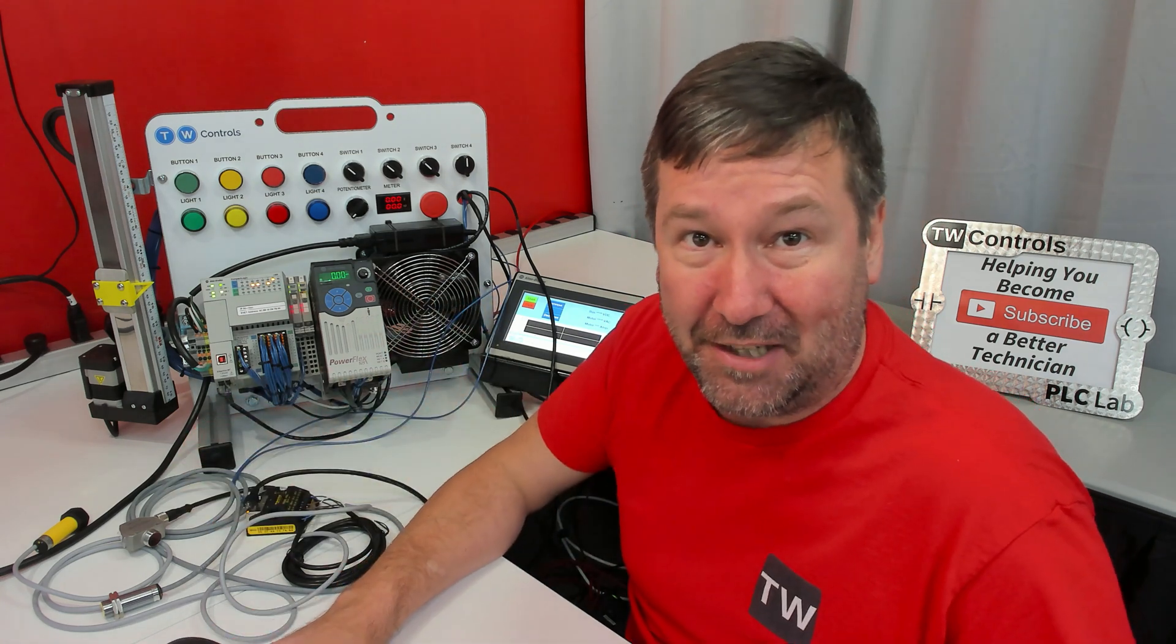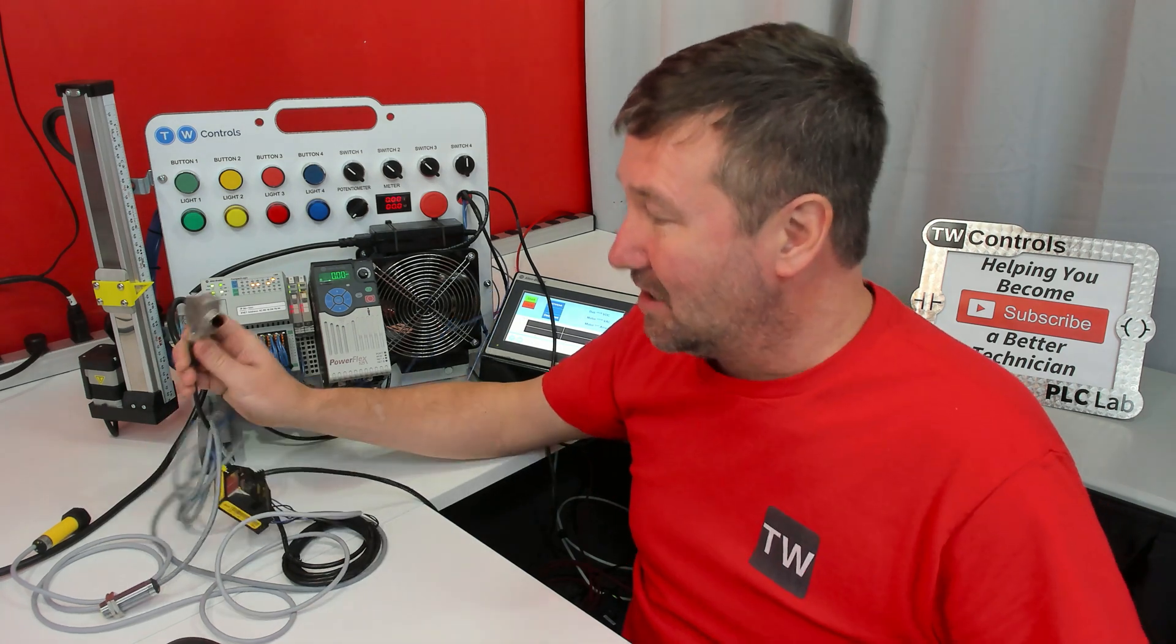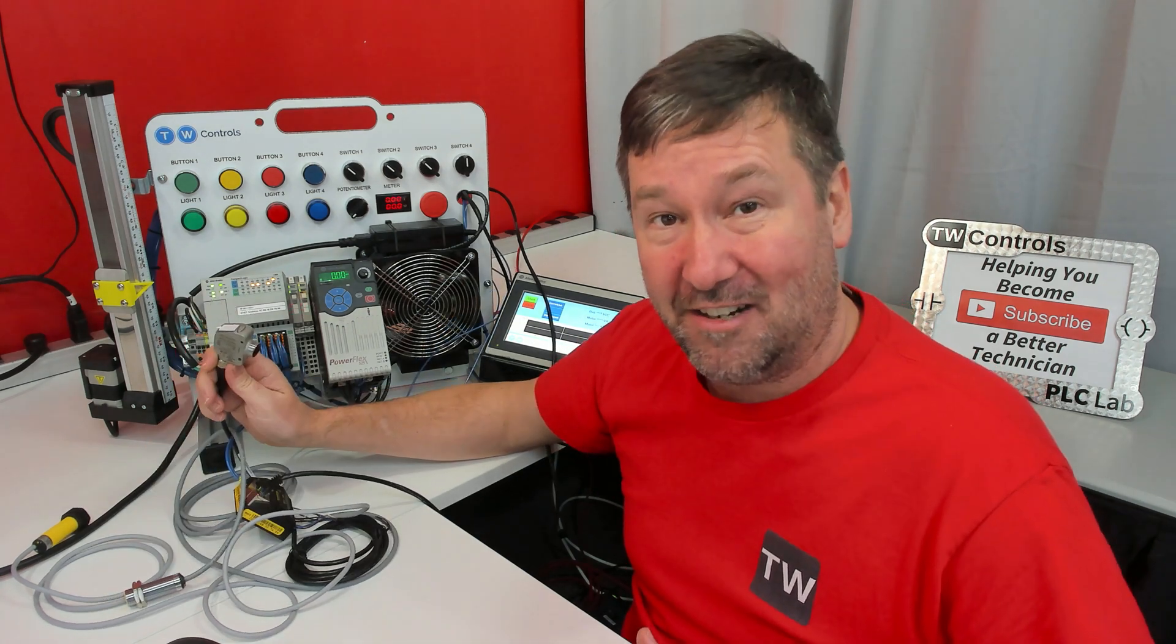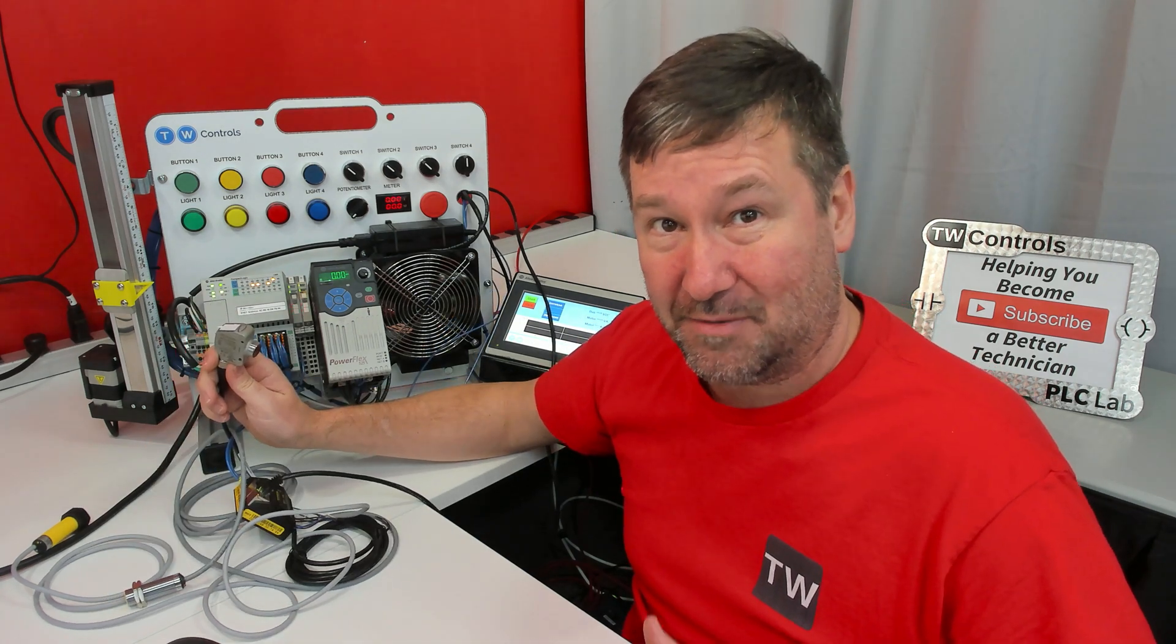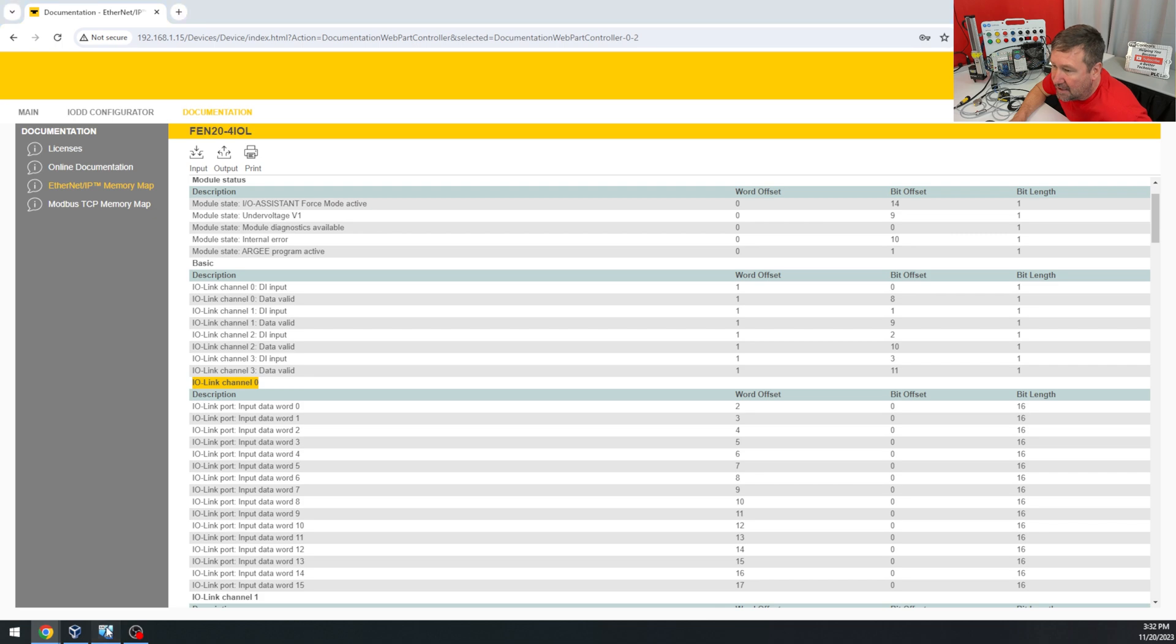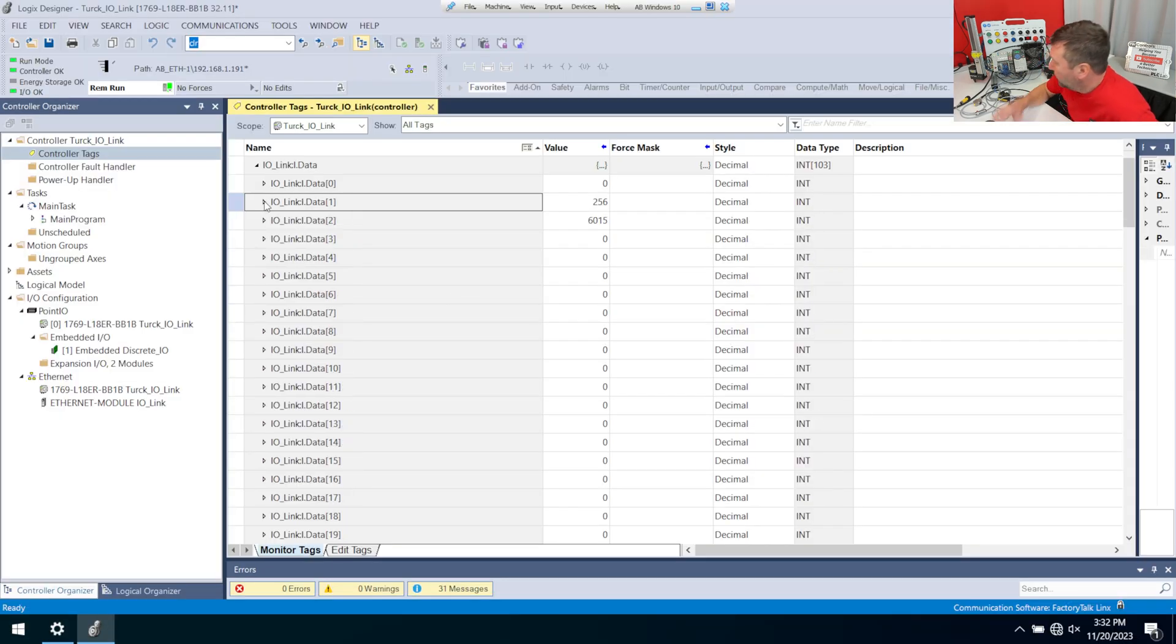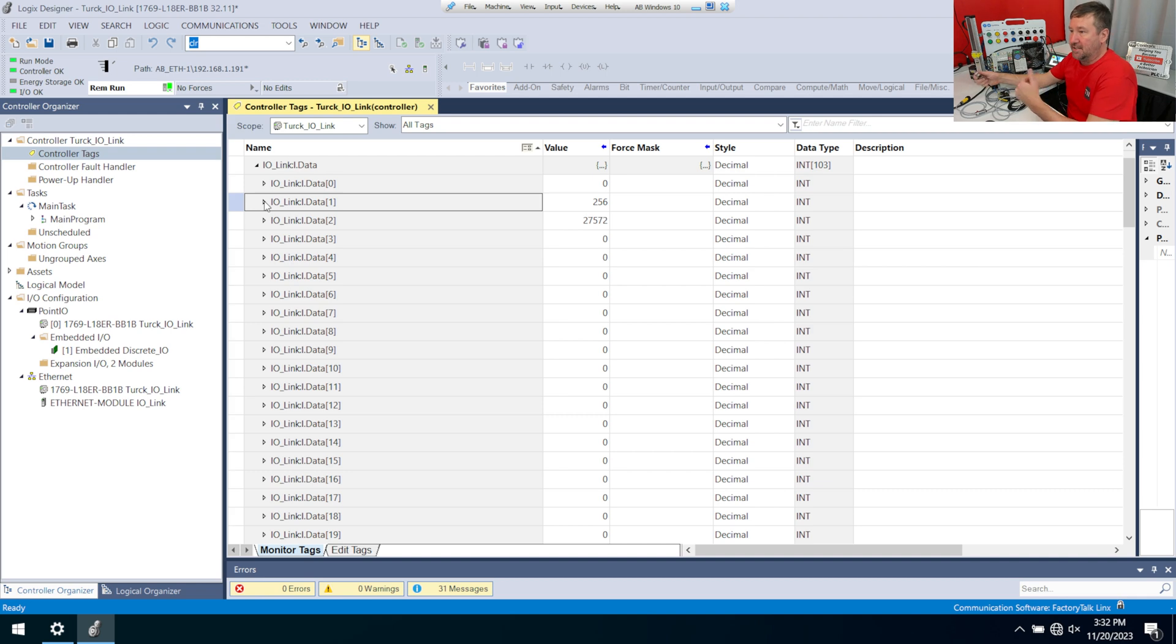But let's see what we can learn about this IO-Link sensor without ever opening a manual. Now the IO-Link data for channel zero is going to be words two through 17. So if we look over here at two, then we can see it is showing something. And as I get closer to it, the number is going down, and as I get further away, the number is going up.